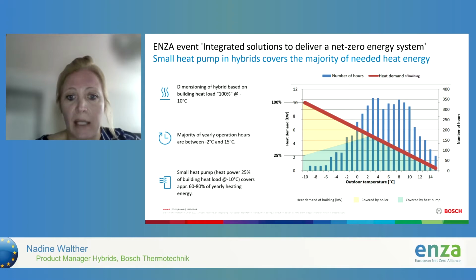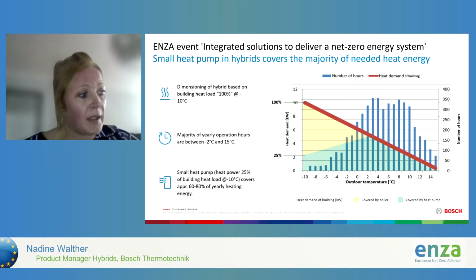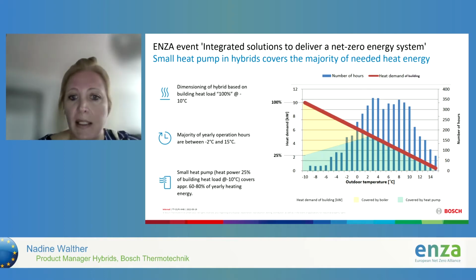So, for example, at -6 degrees, the number of hours the heat pump is being operated is 25, and 2/3 of it is covered by the boiler, and 1/3 is covered by the heat pump. And when multiplying those hours with the performance share of the heat pump, you achieve 60 up to 80% of the yearly heating energy being covered purely by the heat pump. So that is a big advantage. It's important that the heat pump is not only running in the bivalent alternative mode, but also in the bivalent parallel mode. So that also in colder temperatures, such as for example -4 degrees, an energetic contribution comes from it. So that is also important to tell.